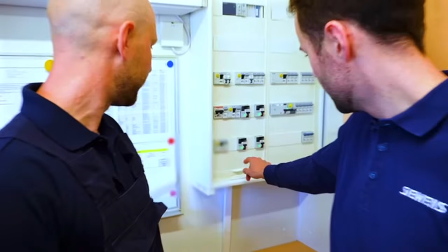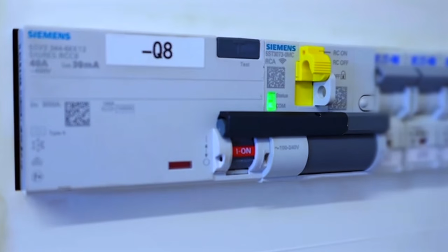The clever Centron also has other capabilities. You can reconfigure it for a change of circuit using an app on your phone. You can change its rated current, tripping limits, or any other behaviour. You could, for example, program it to ignore certain peaks of high inrush currents, meaning you can design a circuit with a lower rated current. This would be useful and economical for circuits with brief inrush peaks. You can also monitor the breaker and switch it remotely, as well as connect it to building management systems.